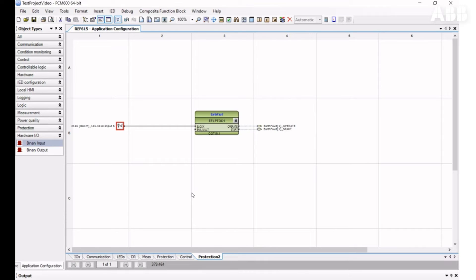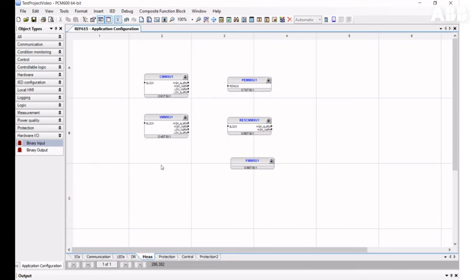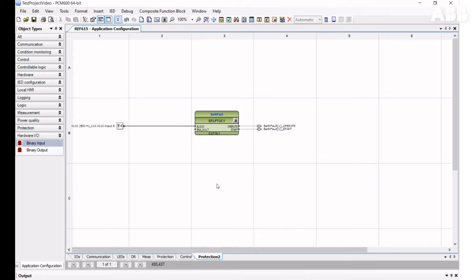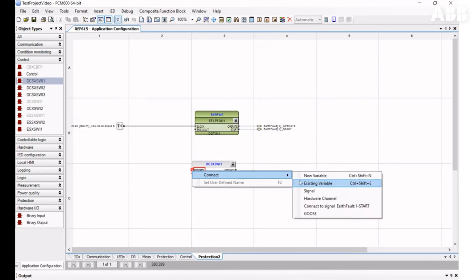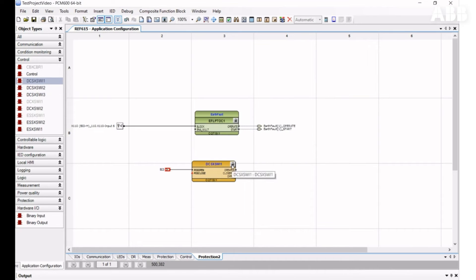A function block may be one of three colors. It may be gray when it's not connected to another element — not all function blocks need to be connected, they just have to exist in the configuration. It may be green when it is connected to another element. Or it may be yellow when it's connected to some element but not all mandatory inputs are connected. Inputs which must be connected are marked with a red triangle.